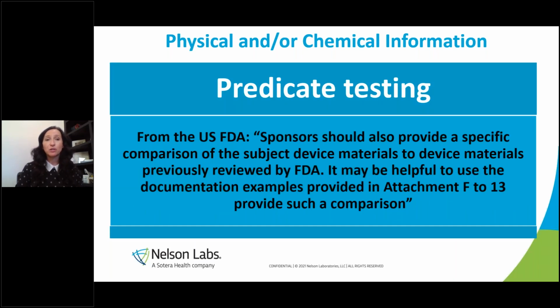Predicate testing: I just put this quote up here from the US FDA as an example. The FDA says if you do predicate testing, you have to provide a specific comparison table, and they like a side-by-side. This is the device that was tested, here's our current device, here's what's different, and then a justification for why the testing applied. I put that up there to highlight that the agencies are open to using comparison data to support the safety of the subject device.